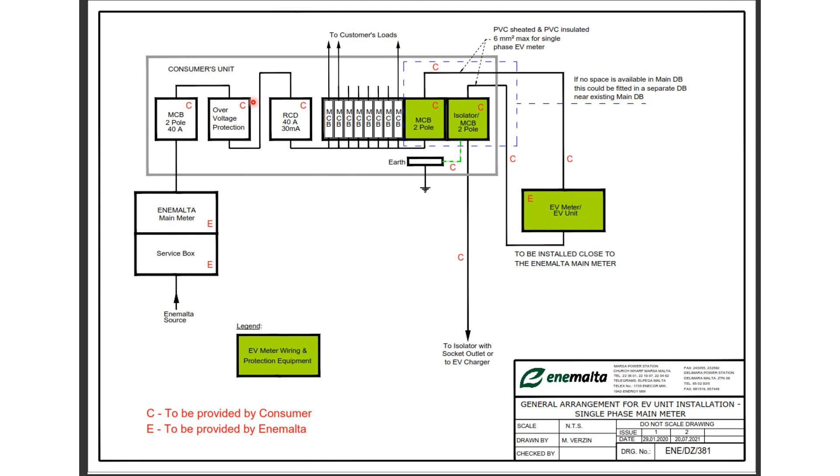The scope of the surge protection is to protect against very fast transients, against very fast changes in the voltage which are not covered by the overvoltage protection device. The overvoltage protection device usually has a minimum delay, a minimum reaction time of 100 milliseconds.